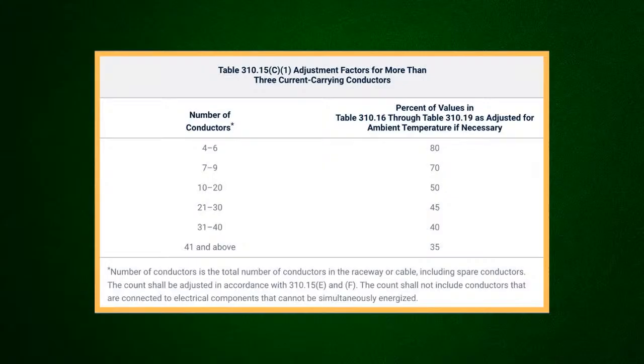So if you go over and look at 334.80, that's where you get into the ampacity of your non-metallic cable. It tells you that's determined in accordance with 310.14, and so on. And then it tells you the ampacity shall not exceed that of the 60 degree C rated conductor. Then it says the 90 degree C rating shall be permitted for your ampacity adjustment and correction calculations. Okay, so we all know that. Now, there's a second paragraph that says where you have more than two non-metallic cables containing two or more current carrying conductors installed without maintaining spacing through the same opening in wood framing, now listen to this, that is to be sealed with thermal insulation, caulk, or sealing foam, then the ampacity correction factors need to apply at this point.